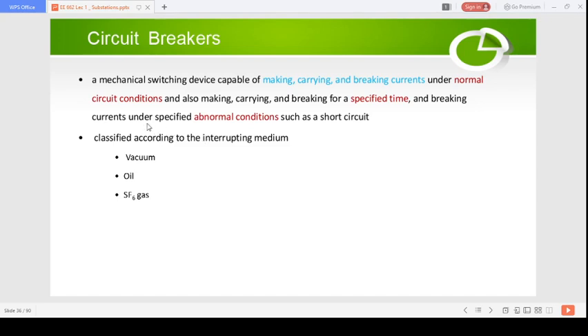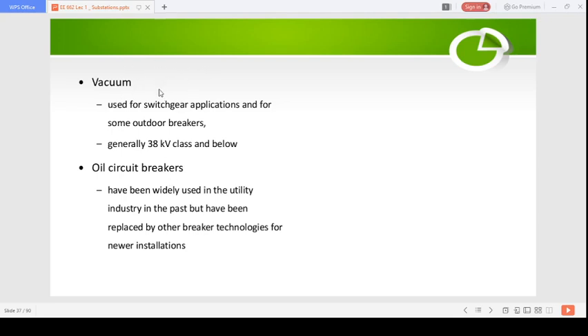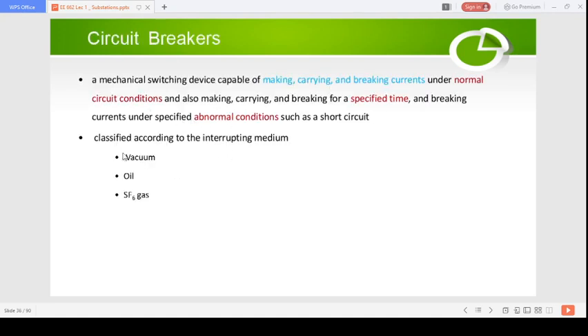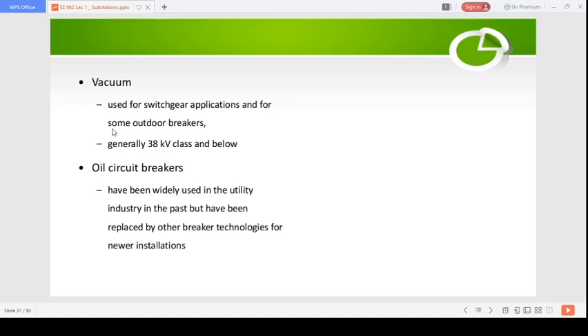Circuit breakers can be classified according to the interrupting medium. You can use either vacuum, oil or SF6 gas as the interrupting medium. Vacuum breakers are used for switchgear applications and for some outdoor breakers. They are generally used in the 38 kV class and below. So if the voltage is 38 kV or below, you can use vacuum circuit breakers.